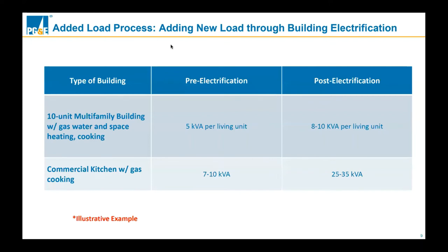Let's say you have a commercial kitchen with gas cooking and perhaps gas water heating. Pre-electrification, you might see somewhere between 7 and 10 kVA. Post-electrification, after electrifying your cooking, maybe even your water heating, you might see somewhere between 25 and 35 kVA. So there is a step up in usage as a result of electrifying. This example is focused just on building electrification.